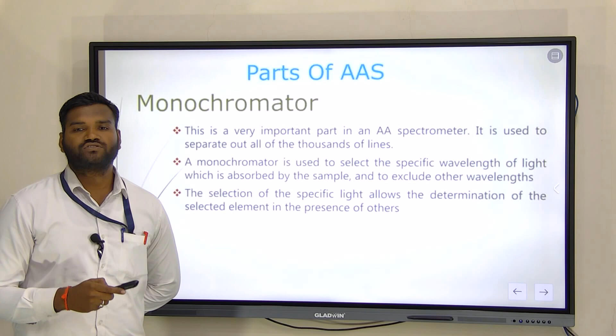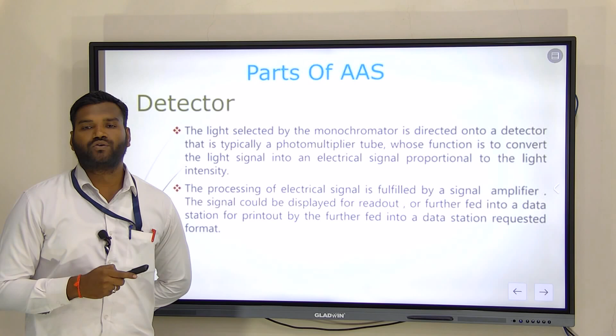Next, the detector. The light selected by the monochromator is directed onto a detector, that is typically a photomultiplier tube, whose function is to convert the light signal into an electrical signal proportional to the light intensity. The processing of the electrical signal is fulfilled by a signal amplifier, and the signal could be displayed for readout or further sent to the data station for printout.